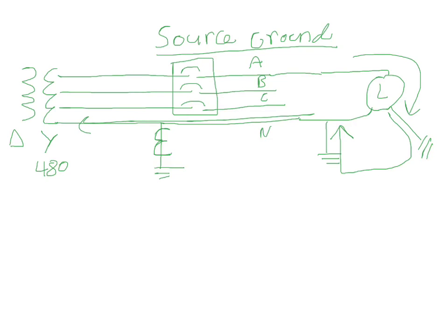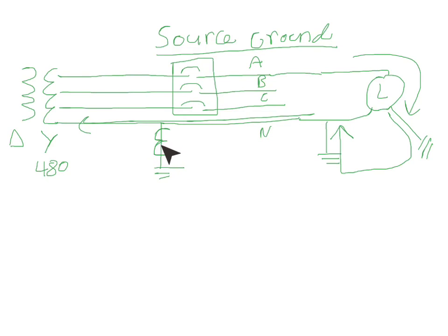I mean, obviously you might have a surge on phase A if it's a big ground fault and it might trip on something else, but you want it to trip on the ground fault. That's the purpose of this ground CT right here in the source ground scheme. Otherwise the system is pointless.